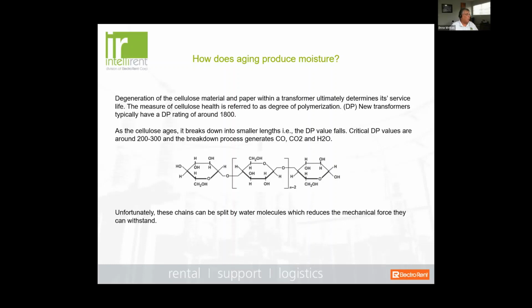Well, degeneration of the cellulose material within the transformer ultimately is going to determine its in-service life. We measure the strength of the cellulose in the paper in terms of what we call degree of polymerization, or DP. And the strength of that insulation is measured, and a brand new transformer should have a DP rating of about 1800. But as the cellulose starts to age, it breaks down into smaller chains or links, and the DP values start to degrade. And if you get a DP value of anywhere from 200 to 300, basically your transformer has reached the end of its life.